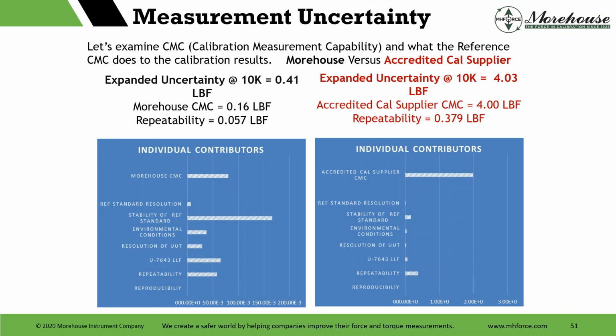And when we talk about measurement uncertainty, if we examine Morehouse versus another accredited supplier, look at what happens. Look at all this stuff here. Look at these graphs. Stability of the reference standard when Morehouse calibrates something is usually the highest, but look at these numbers. Expanded uncertainty at 10K on a 10K load cell is 0.41 pounds of force when Morehouse calibrates it, and we have a CMC of 0.0016% times 10,000. Repeatability was this. And the accredited supplier is starting at 4 pounds. Repeatability point this, expanded uncertainty 4.03.